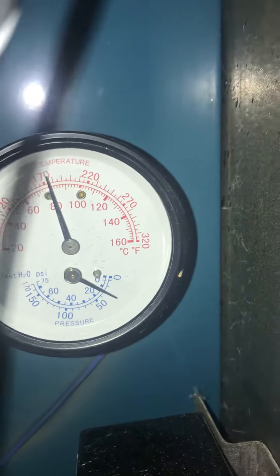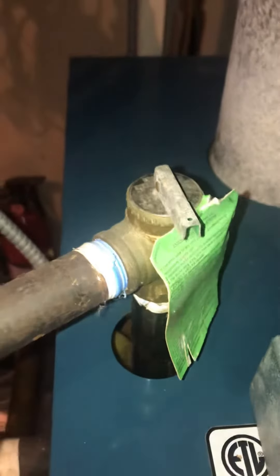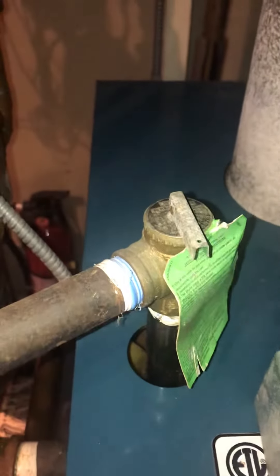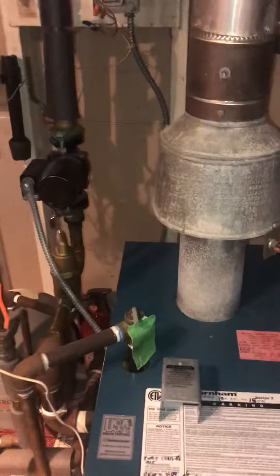The tricky thing is on that bottom needle — the scale goes way up to over 60 pounds. This relief valve up there will pop off if it goes above 50. So anyway, there's a little more info on boilers.